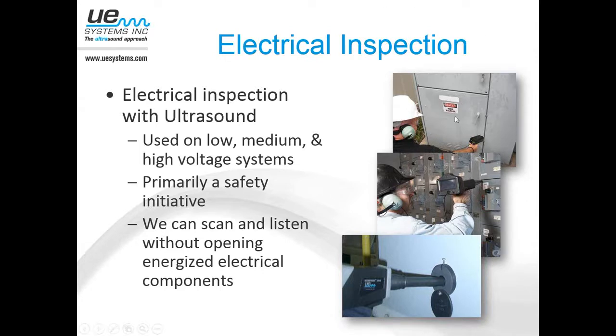If you take a look at the top picture here, you can see most enclosed switchgear has an air gap around the door, or in some cases there are ventilation louvers, and you're able to actually hear the sound from what's going on inside of that cabinet. So again, as a safety precaution, before those cabinets ever get opened, many of the companies we work with on a regular basis have made that part of their electrical safety and infrared safety program. Scan it with ultrasound first before you ever open the cabinet.